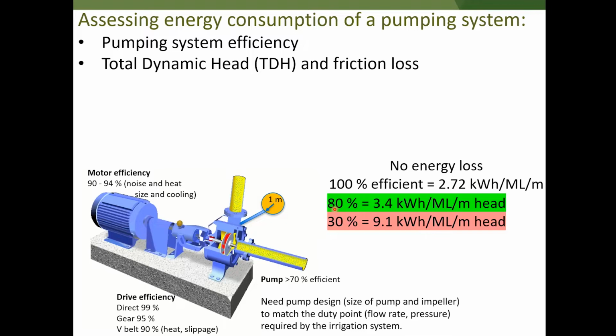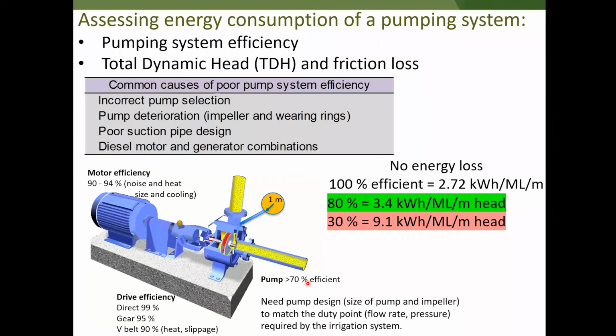The range of efficiencies we've seen in our assessments are from as high as 80%, which is really good, down to as low as 30%. So an 80% efficient pump will use a bit over 3 kilowatt hours per megalitre per metre of head, compared to a 30% efficient pump will use over 9 kilowatt hours per megalitre. And that's all related to how well the system's set up and matched to the duty point of the irrigation system. So some of the common causes of poor pump system efficiency is incorrect pump selection.